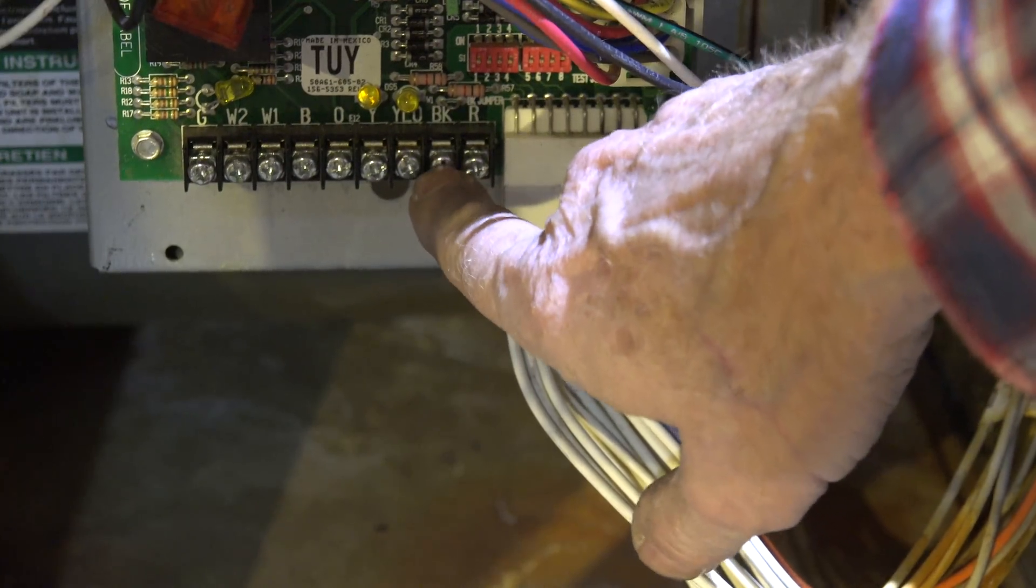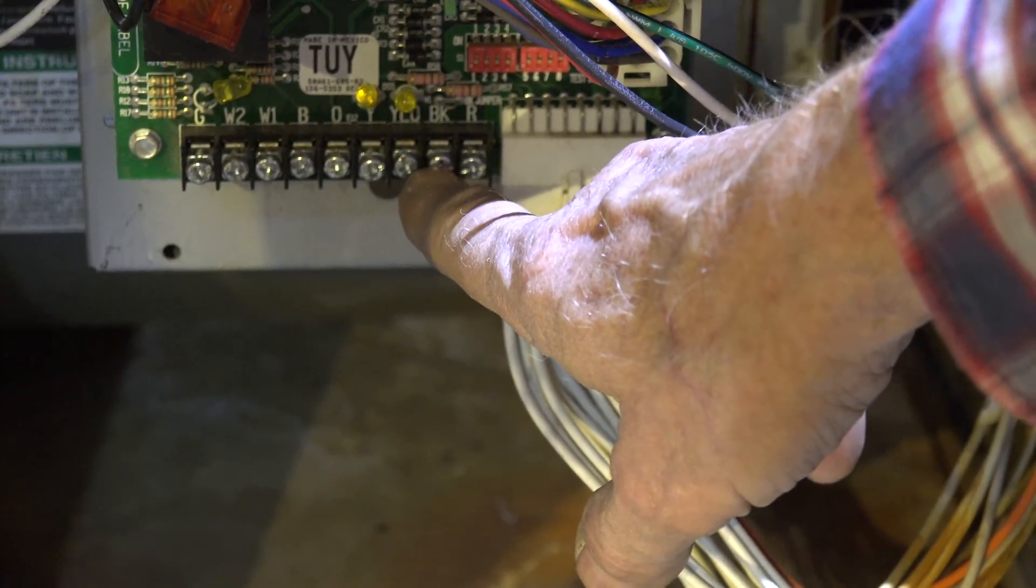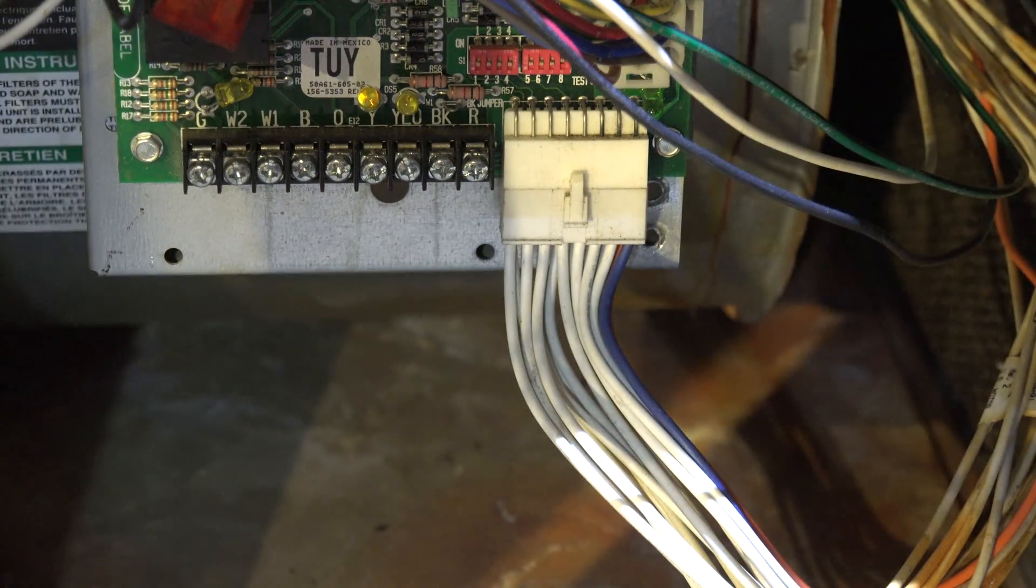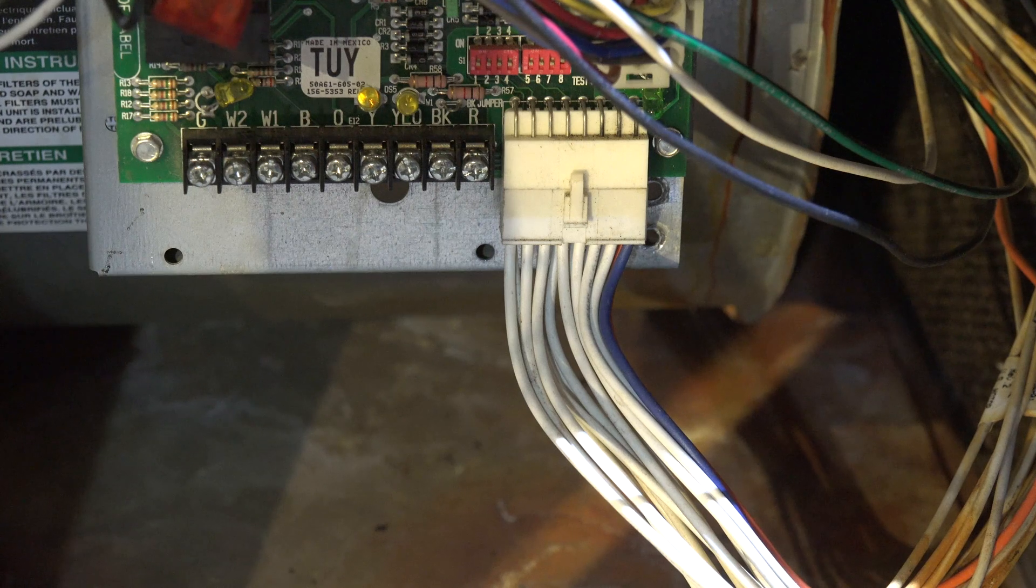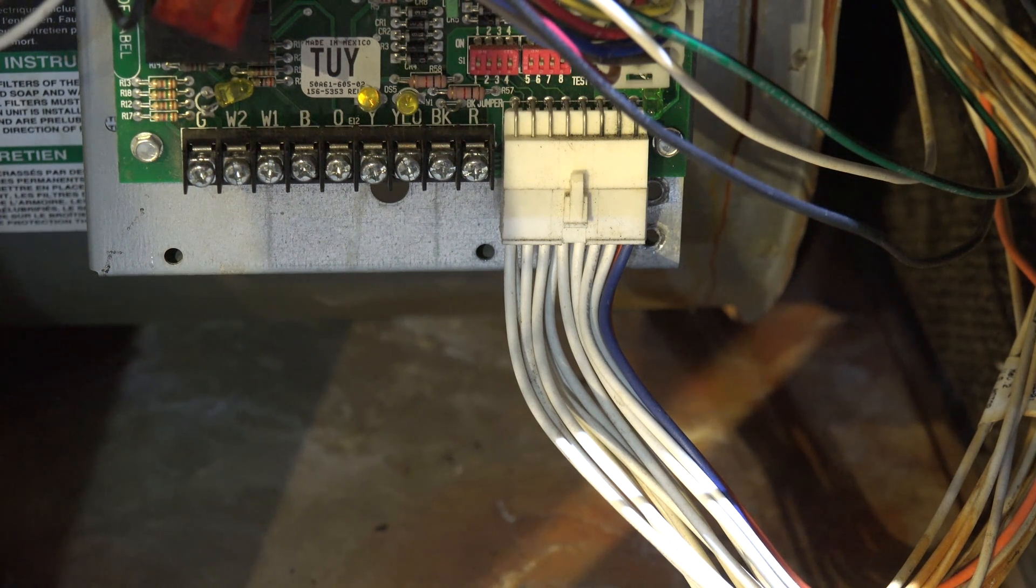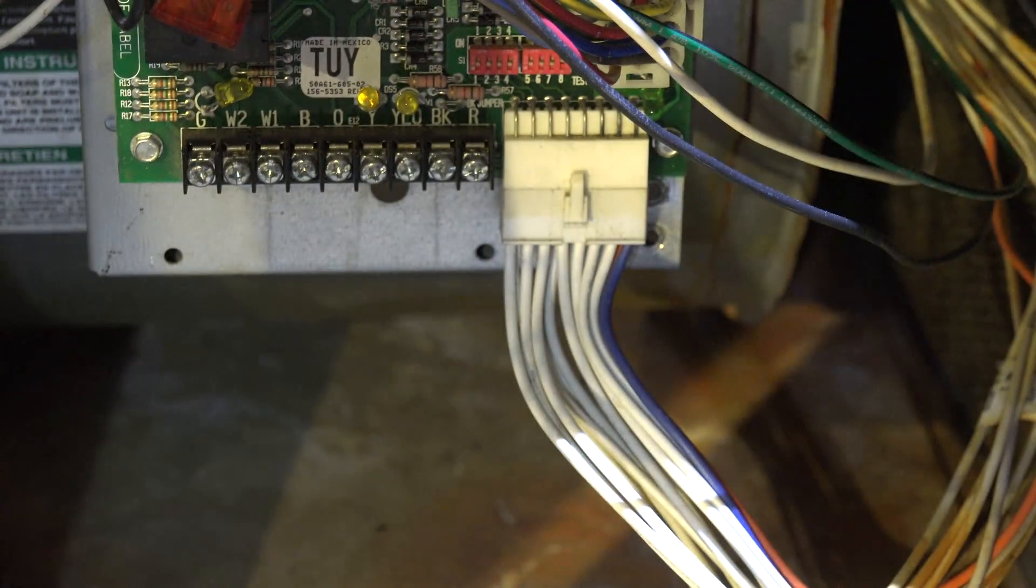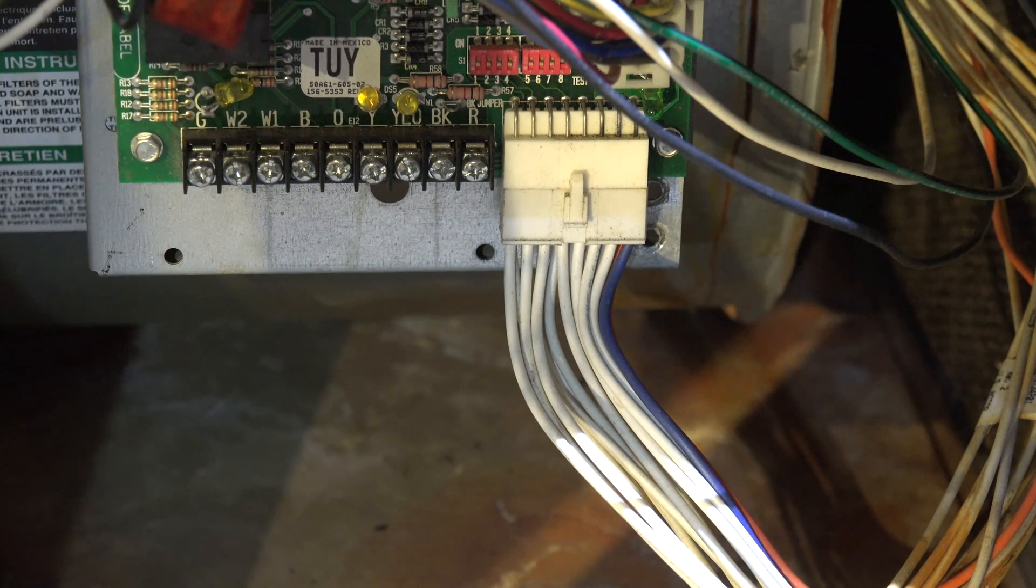Here we have an R where your red wire would go to, and we have right next to it a black. That's your common right there. It could be BK like that, or it could be C depending on the brand and model of the furnace.